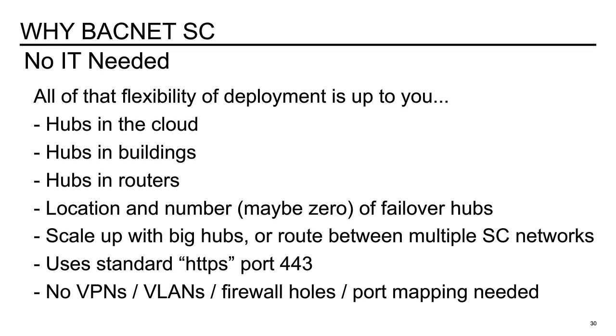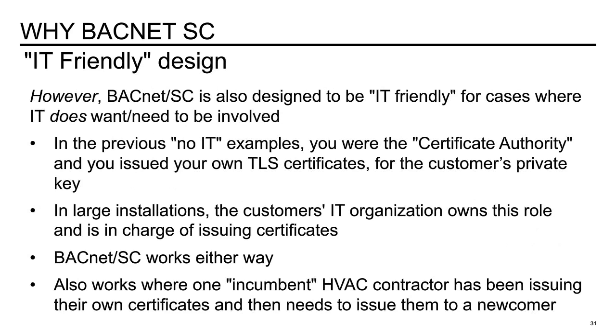However, BACnet SC is also designed to be IT friendly for cases where it does require IT involvement. In the previous no-IT examples, you were the certificate authority and you issued your own TLS certificates for the customer's private key. In large installations, the customer's IT organization owns this role and is in charge of issuing the certificates. So with BACnet SC, you can do it either way. You can manage it on your own, or you can involve the IT department in managing the certificate. This also works where one incumbent HVAC contractor has been issuing their own certificate and then needs to issue them to a newcomer, and the reason is the owner is going to be the certificate authority.